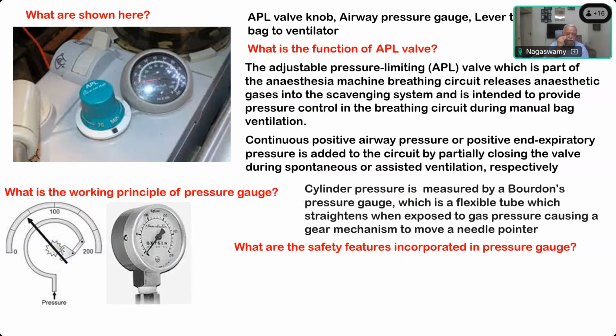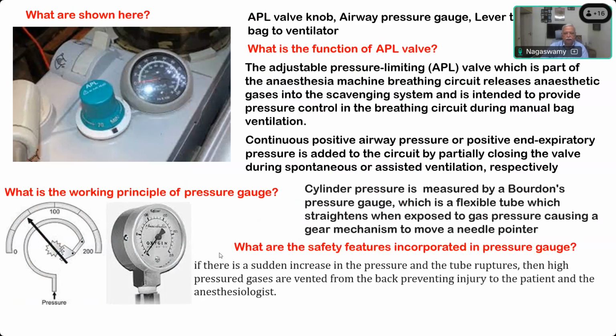And in modern machines, instead of a straight mounting, they have an angulated mounting for easy visibility. Okay. So here, if you see, this is going straight, but there will be a stem here, then the gauge will be in an angulated position so that you can easily see it from any angle. So if there is a sudden increase in the pressure and the tube ruptures, then high pressure gases are vented from the back, preventing injury to the patient.